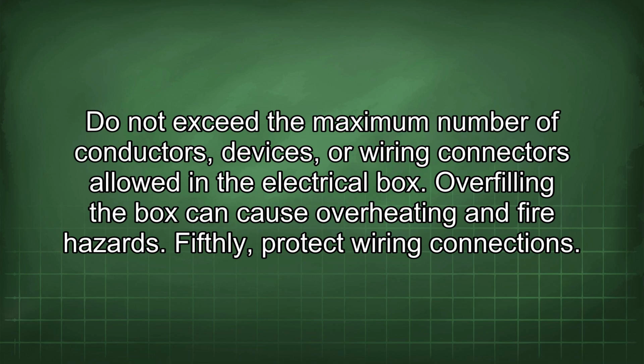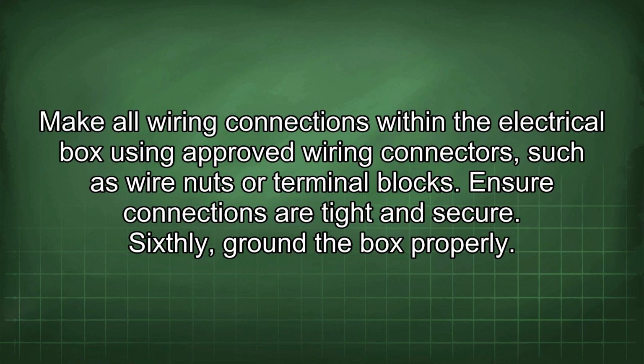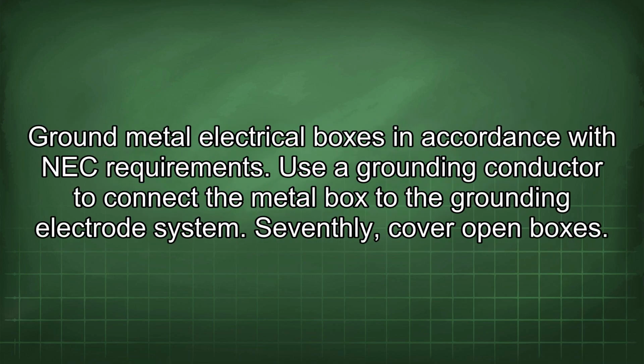Fifthly, protect wiring connections. Make all wiring connections within the electrical box using approved wiring connectors, such as wire nuts or terminal blocks. Ensure connections are tight and secure. Sixthly, ground the box properly. Ground metal electrical boxes in accordance with NEC requirements. Use a grounding conductor to connect the metal box to the grounding electrode system.